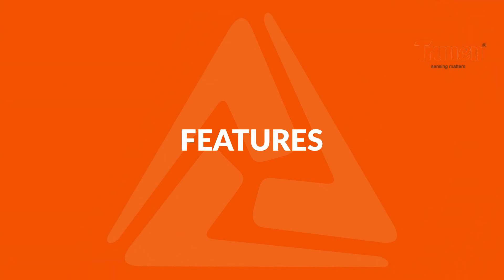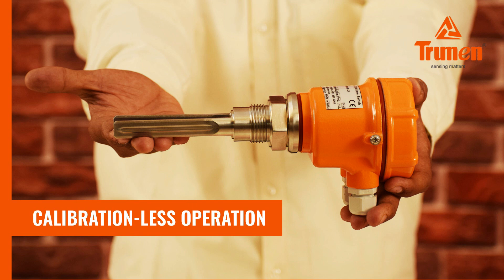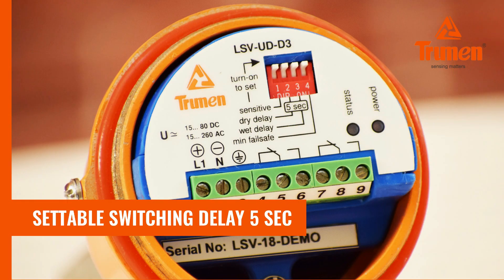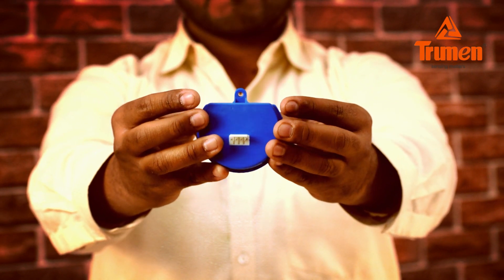Features: The Trumen vibrating fork is compact in size with calibration-free operation. Universal power supply on the same terminal: 15 to 80V DC or 15 to 260V AC. Inbuilt settable switching delay for 5 seconds. Tropicalized sealed electronic module for easy maintenance.